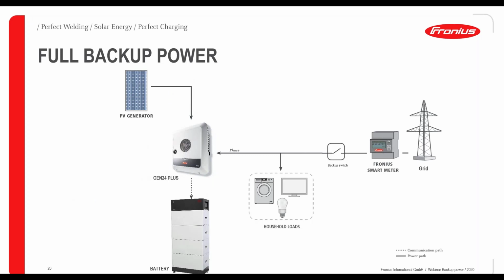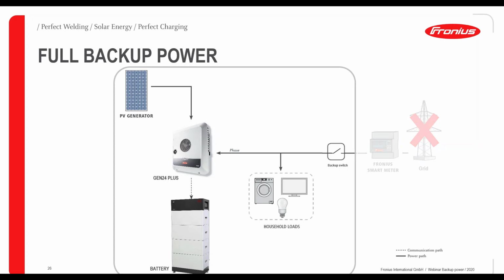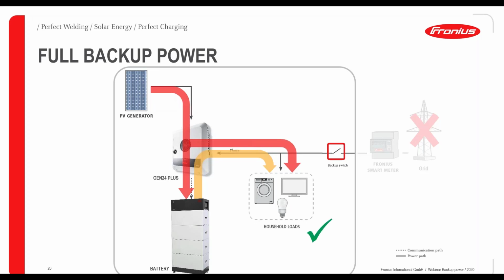Then the full backup power solution: here a battery is needed, and of course the backup power switch is also required. In this case, when there's a blackout, the system's backup switch would switch over, and the system will be supplied from the PV generator to the battery and to the loads, as well as from the battery to the loads, of course, at nighttime. This is the full backup power solution where we supply all household loads with this system.